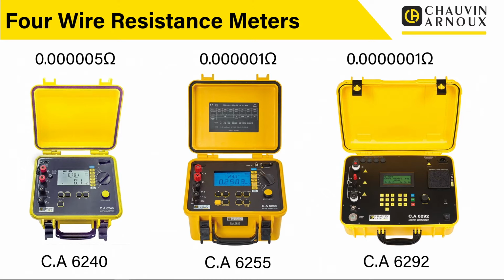If we then step up one to our 6255, we're down to 1 micro-ohm. So we can actually measure down to a single micro-ohm, hence the name, micro-ohm meter. And if we go up another step to our 6292, this can measure to 0.1 of a micro-ohm. That's 0.1 of a millionth of an ohm, or 100 nano-ohms if you want to put it that way around. So we're really getting into those low resistance measurements. You can see the difference when we're talking about low resistance measurement. A lot of times people say anything under 100 ohms is a low resistance. These are truly low resistance measurements, and this is the category we get into with proper micro-ohmmeters and 4-wire measurement. It does show you the difference in the information that you could get if you stepped into this type of measurement.